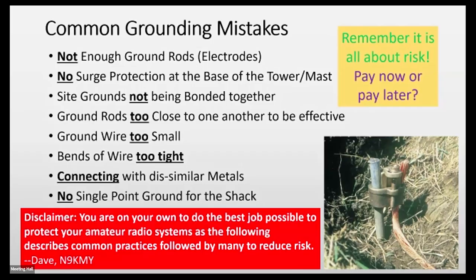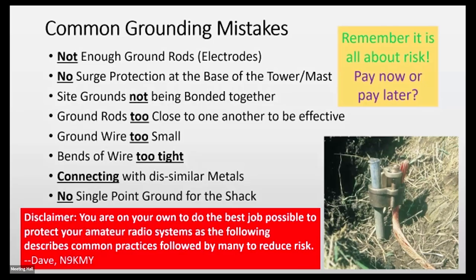Site grounds not being bonded together — again, I did have this in place, but it's something we talked about — and the ground wire being too small. It's accepted practice in the amateur community to use no lower than number 6 stranded wire for grounds. If you can afford something heavier, that's great, but nothing smaller than number 6 in diameter. You need that surface area of the wire to get a good mechanism for ground, and I use number 6 throughout. Copper isn't cheap today, so understand that, but then again, where's your equipment that you'd want to replace after a hit?